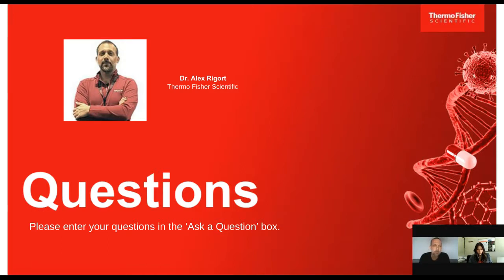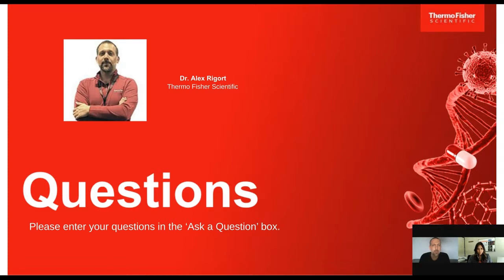Next questions: is the IFLM limited to the Aquilos II, and is it possible to install it on an already-working first-generation Aquilos? The system is made for the Aquilos II, so you would need to upgrade from the Aquilos I to the Aquilos II system. Another question: is it possible to use the fluorescence microscope at the coincidence point, or does the stage need to move? Unfortunately, with current light microscope objectives, they would collide with the pole piece geometry, so we do have to move to an offline imaging position — the stage must move in X-Y to the LM imaging position.